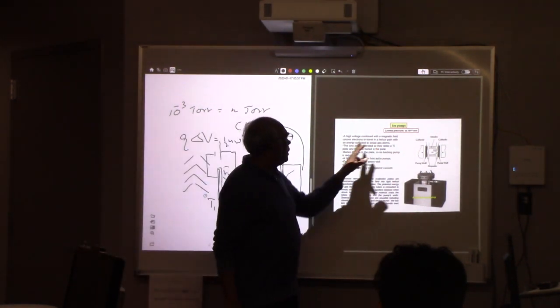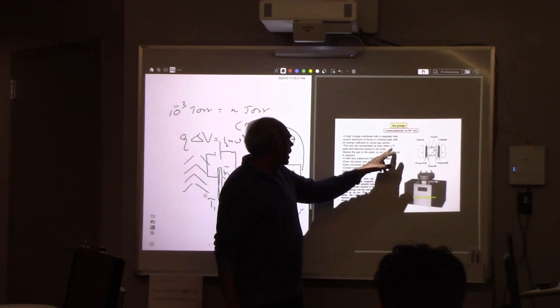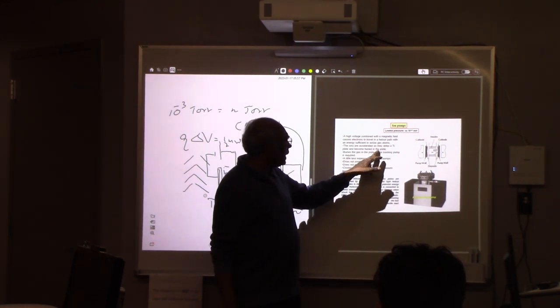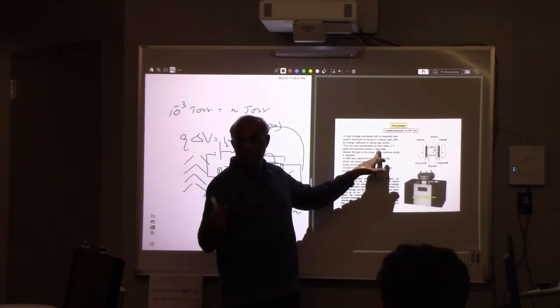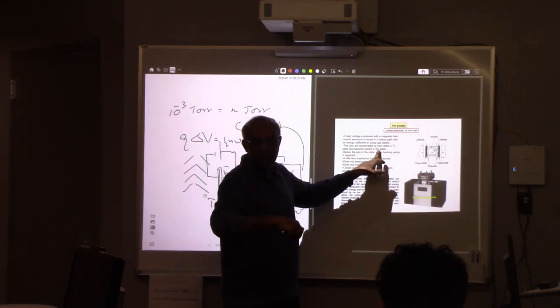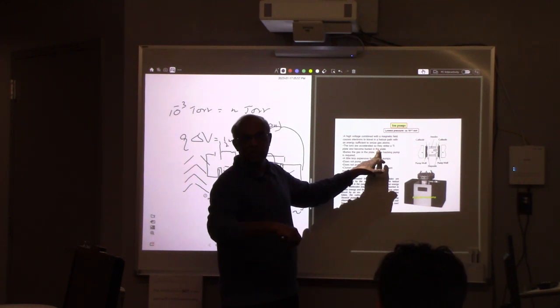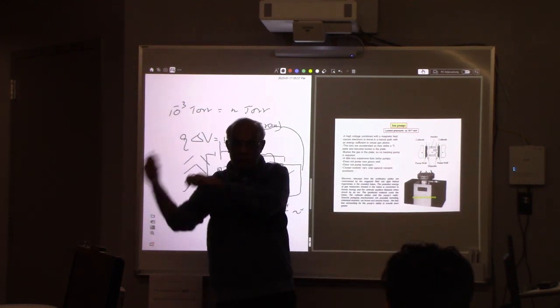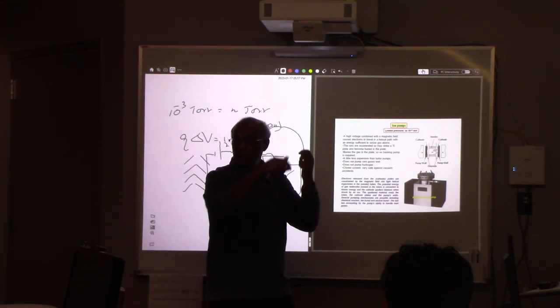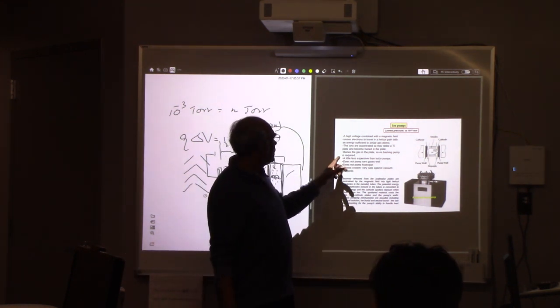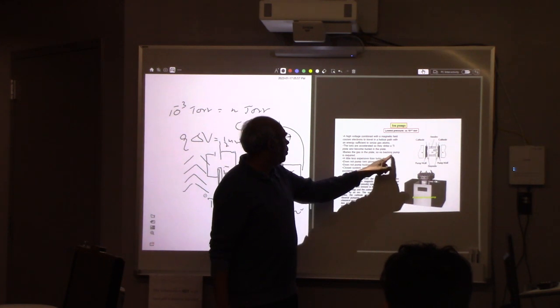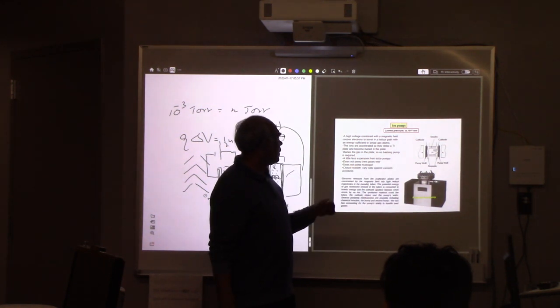So typically, ions are accelerated, strike the titanium plate, and become buried in the plate. Buried means buried with gas molecules, right? That's how gas molecules get pumped out - not by pumping out, but by being buried in the titanium. Gas gets buried in the plate, so no vacuum pump is required.